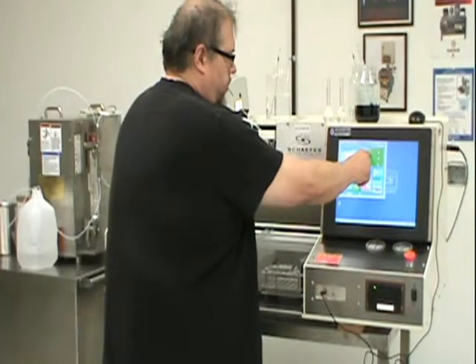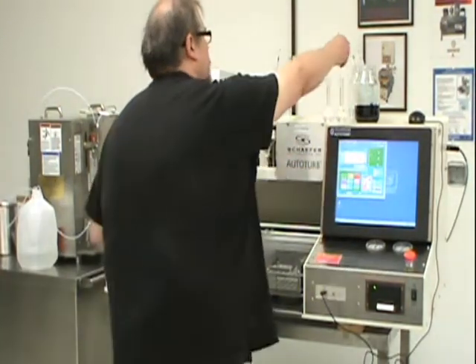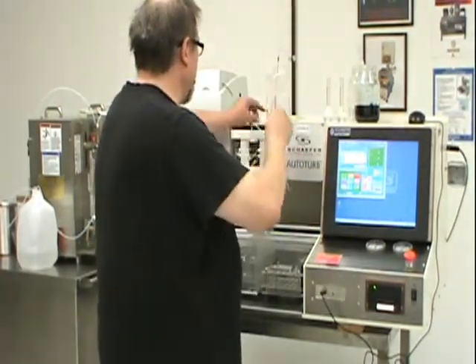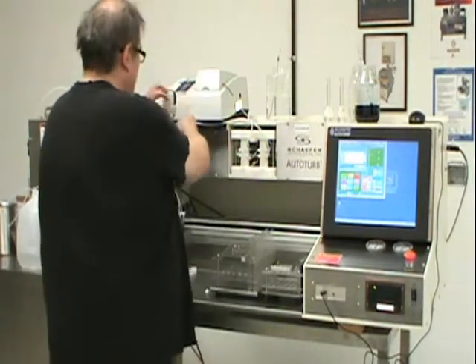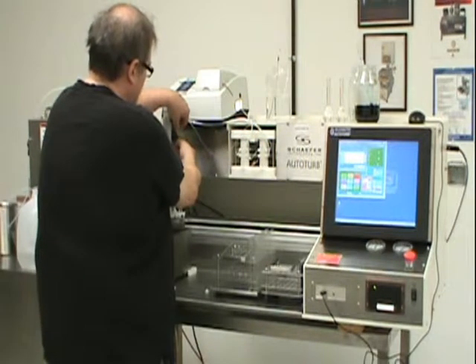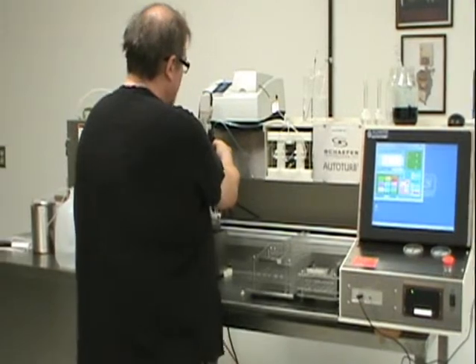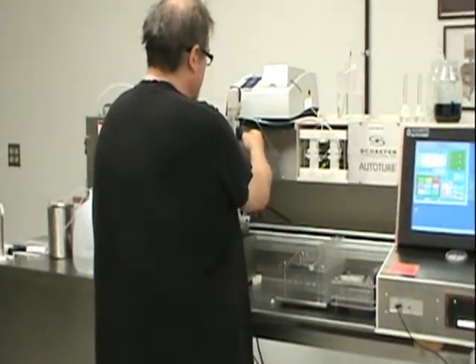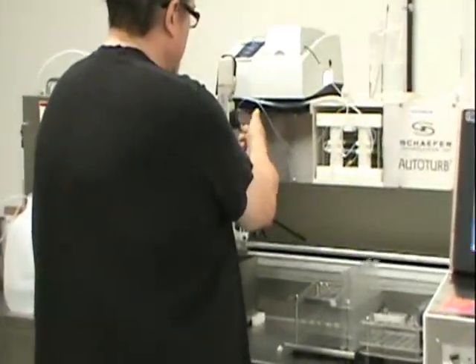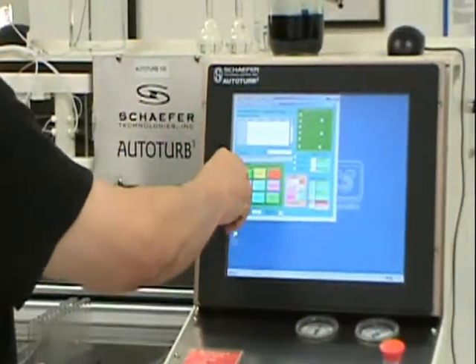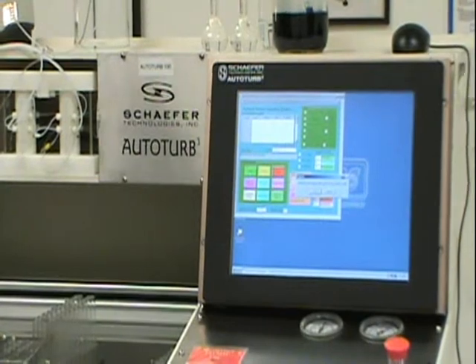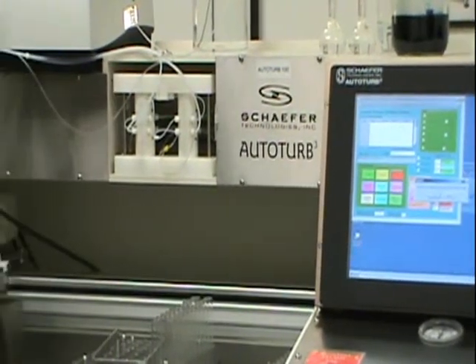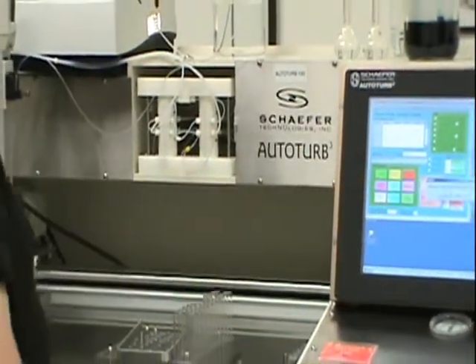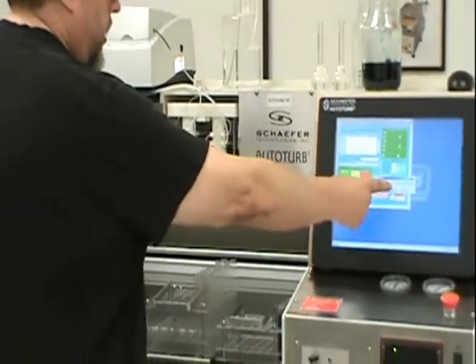So we select diluter alternate, place the diluter probe in the probe holder, and it fits in so the little black piece on the probe is flush with the top of the metal unit. And then we press start to start the test. It tells us when we're executing an alternate test. If we made a mistake, we can just press cancel and back out of it. And we press OK.